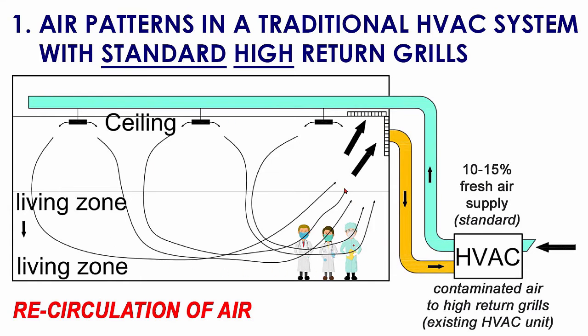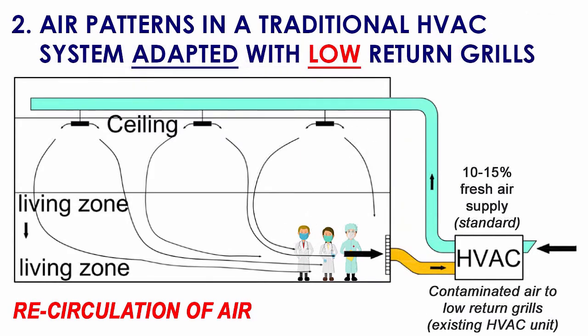Let's look at what happens if we lower the return grills. We can see here a return grill that has been installed low. You can immediately see that the air pattern has changed. The air that is coming from the ceiling and is moving through the living space stays low. So the contaminants in the air like dust particles, VOCs, carbon dioxide, bacteria, and viruses, they move with the air low toward the return grill, which is better for our nurses and doctors and all other medical personnel. It is lowering the risk of infection. A note on these adaptations, they can be temporary.